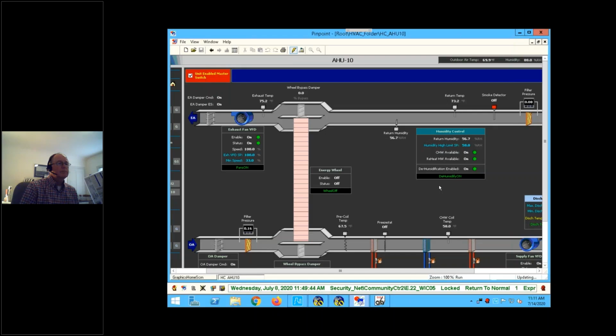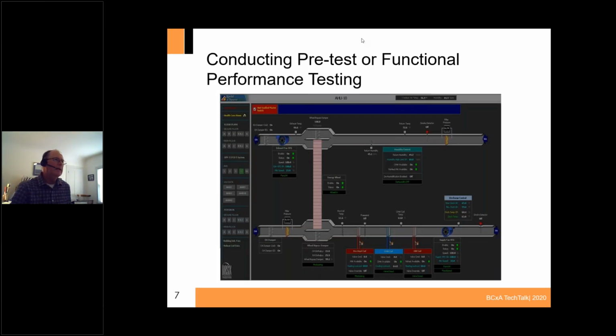So this is just a tidbit of the kind of thing that I have been doing on a regular basis now with the controls contractor, to do a pre-test of the controls, because there's so many things that the engineer doesn't write down in his sequence that certainly need to be tested. In this particular case, I was a little concerned that the wheel wasn't running—why go through the wheel if we can go through the bypass dampers? There would be less static pressure on the system and maybe save a little bit of energy. So eventually I started to make some changes for this system, or make recommendations to the engineer for some changes.